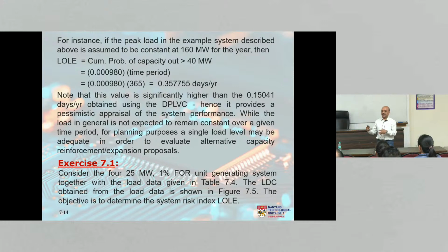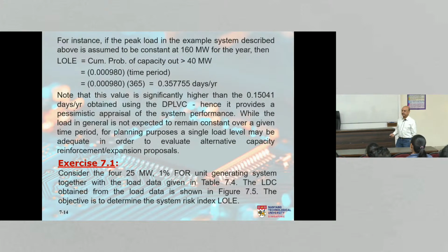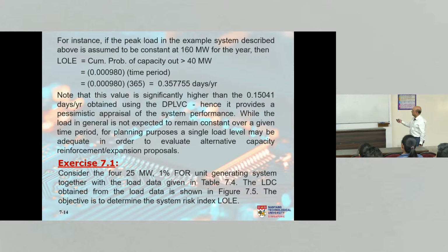But we have at least an analytical method to calculate and to give us the quantitative reliability indices on which we can base our judgment, right? Eventually, of course, you still have to use your judgment, but at least you have the basis for that judgment, okay? So that's what we have done now. We can use any of the load curves, but constant load gives you a pessimistic appraisal. Pessimistic, obviously, you can see the number is much higher, yeah? 0.35, which is almost more than double the number that we obtained using a load curve, straight line curve.